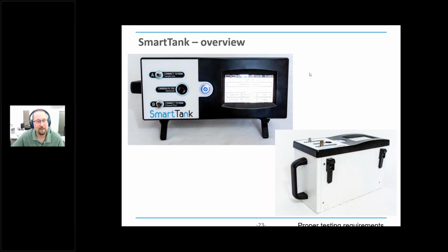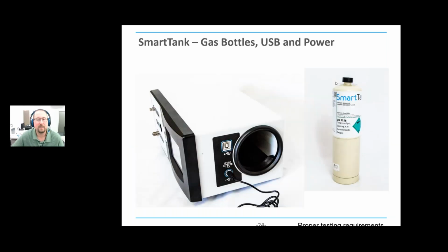Our customers love it, and they're always using it. A lot of them bought it thinking they'd use it once a year for their PMs, but they use it for everything to do with gas monitors, to spot check, and find other uses for it too even. On the side over here, there is a slot to put in a bottle of gas. So you do have to use a gas bottle. The calibration gas is always the best way to calibrate any sensor, no matter what it is, because nothing is more accurate than calibration gas. You can't mix gases on the fly in real time to do a good job, but you should use a calibration gas.